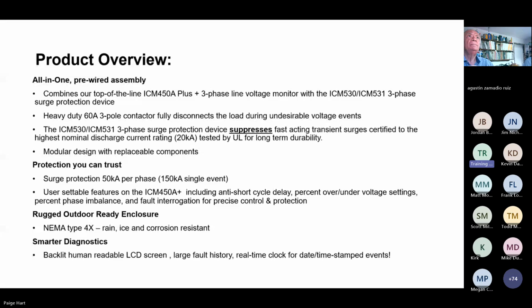You also have a large fault history in there. You have a real-time clock that can tell you what the time and date were for those fault events, which is extremely important when you're trying to diagnose something that's happening at weird or oddball times. For example, I have a customer that was having a problem. He was getting called out at 2 o'clock in the morning every night, or every morning, I should say, because their equipment was shutting down.